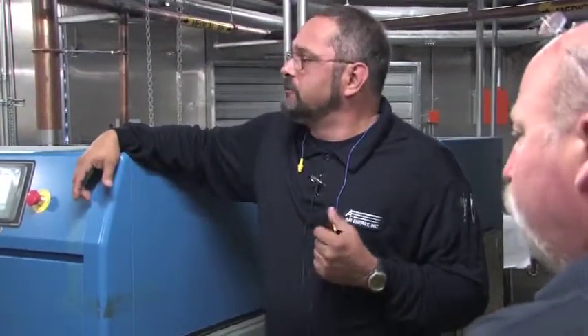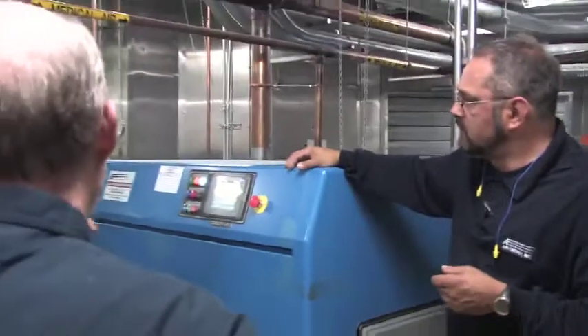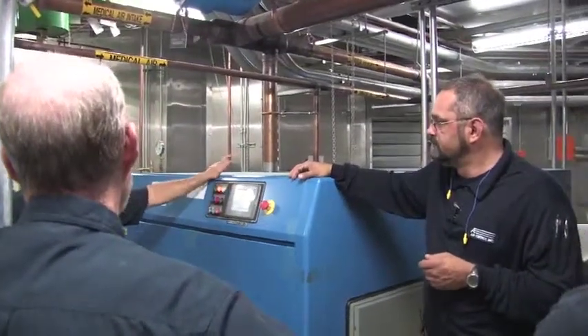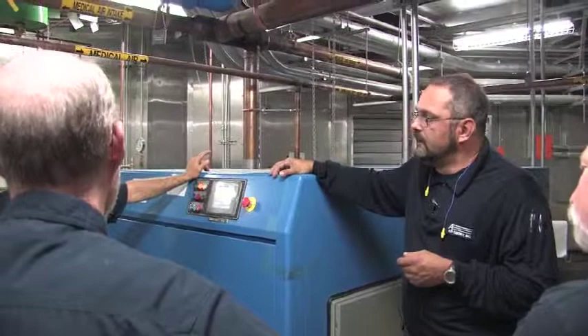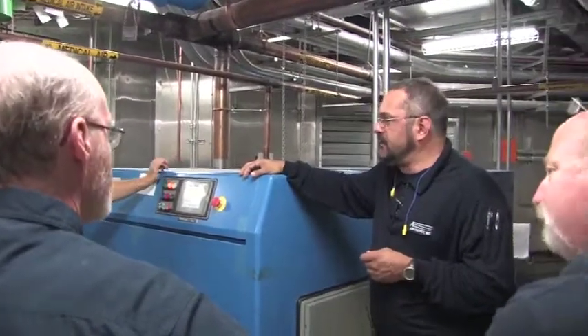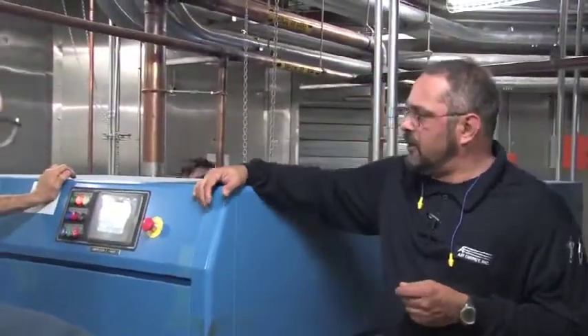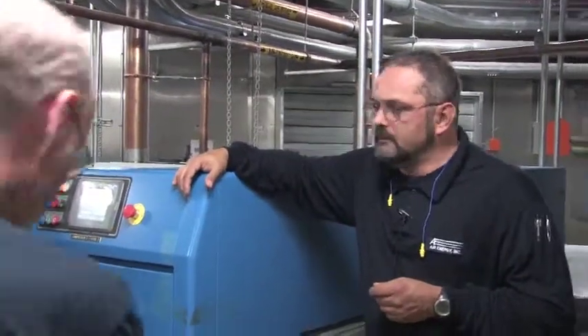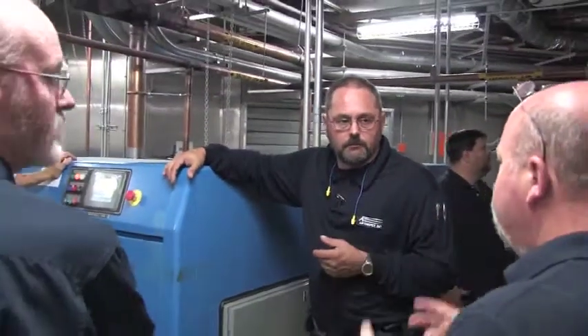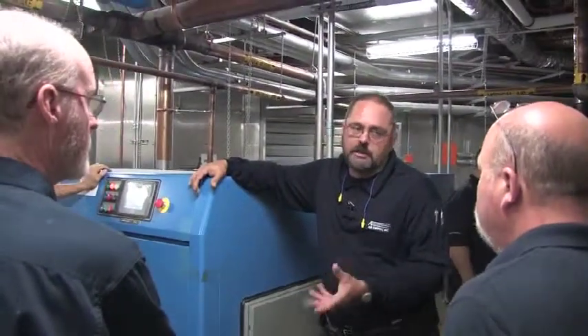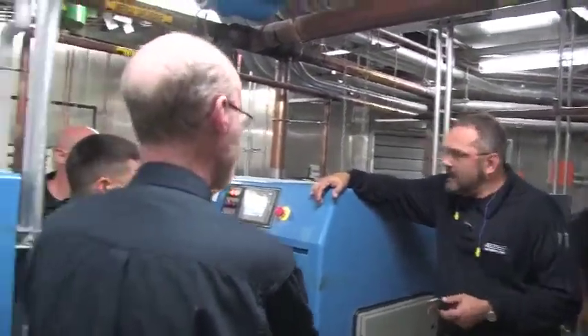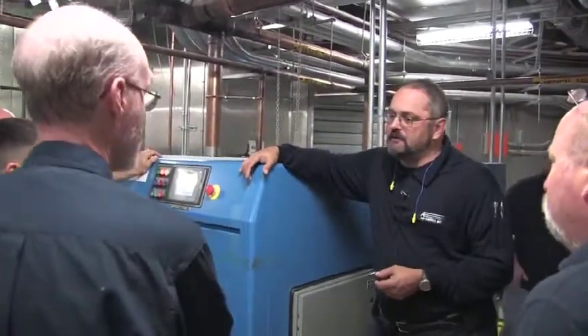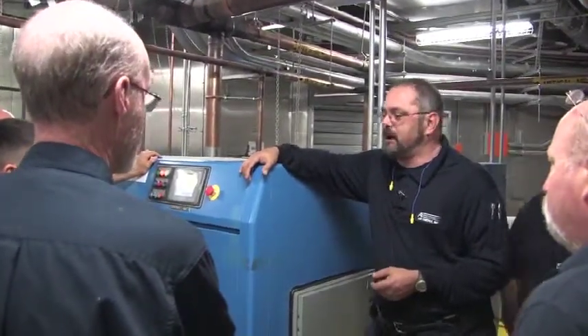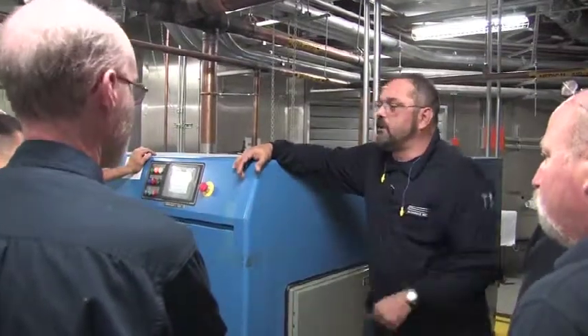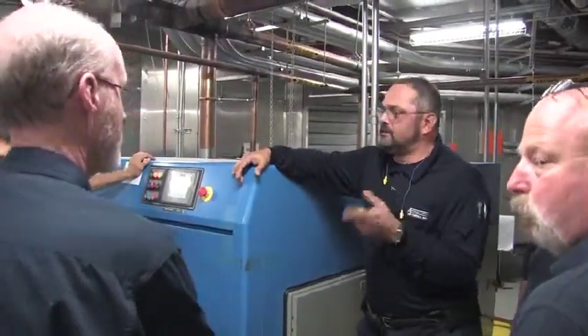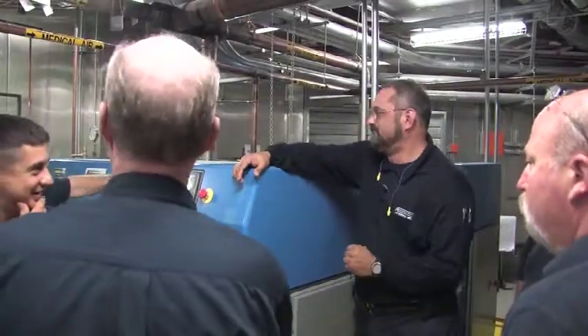How complicated or how difficult would it be to turn one of these other 2 into the master? It's actually a different program that would need to be loaded. How long would it take? A day, 2 days? It's a circuit board, isn't it? It's built into the PLC. Actually, probably the simplest way to do it would be to take the existing modular chip off that machine and throw it in. The downside of doing that would be that the serial numbers and everything else would move over too.